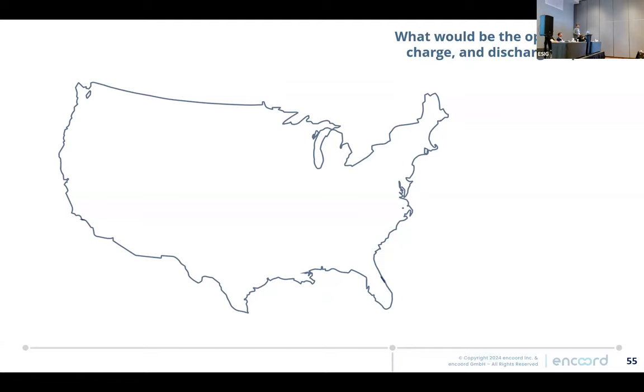liquid air energy storage, where that is indeed true. When you build a liquid air energy storage asset, you can decouple the capacity of the energy, the capacity of the charge, and the capacity of the discharge, because the charge is primarily compressors, the discharge is a turbine, and then the storage is literally reservoirs, containers where you store air at really high pressures and low temperatures.